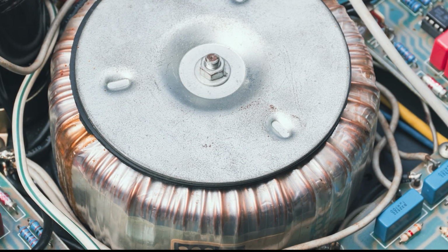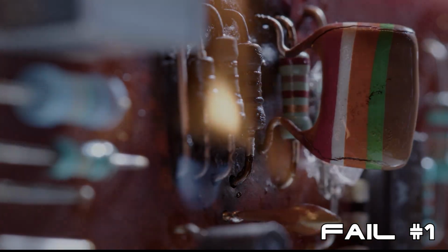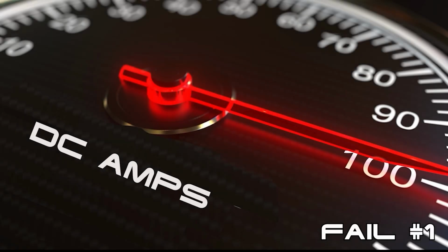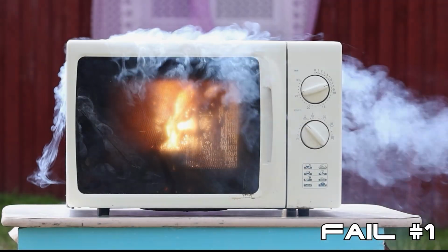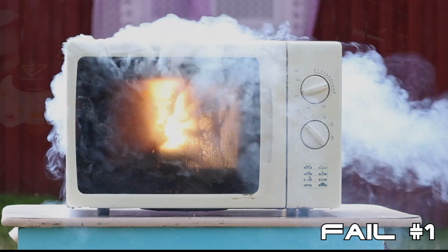And finally, fail number 1. The most important and dangerous issue with high-frequency transformerless inverters is their lack of an iron core, copper-wound output transformer. Without this transformer to provide galvanic isolation between the inverter's DC boost stage and its AC output, during a catastrophic failure of the inverter's control circuitry, or its H-bridge circuit, high amperage DC current can pass through the AC circuit breaker that can not only damage your AC appliances, but can also set those appliances or your EV on fire.